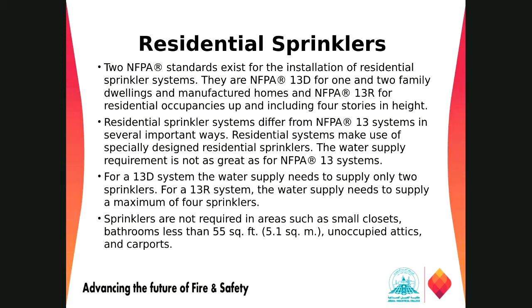The number of sprinklers in NFPA 13D is only 2. Let's say we don't need complete water demand as we saw in NFPA 13R. For a 13D system, the water supply needs to supply only 2 sprinklers. So NFPA 13D is required to calculate for only 2 sprinklers demand, right? So not talking about the whole area or whole building. And 13R requires water supply for 4 sprinklers. This is totally different than our NFPA 13, where we need at least minimum 10 to 14 sprinklers based on the hydraulic demand areas.